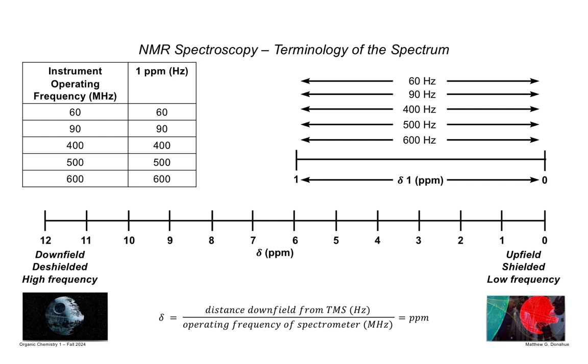So a little bit about terminology and the NMR spectrum. The NMR instrument is basically a big dewar. So if you have like a Stanley Cup or a Yeti or something, that's like a dewar, right? It keeps hot things hot and cold things cold. So it has these surfaces, and inside there's a vacuum, and the vacuum is what sort of mitigates the temperature from the external part to the internal part.